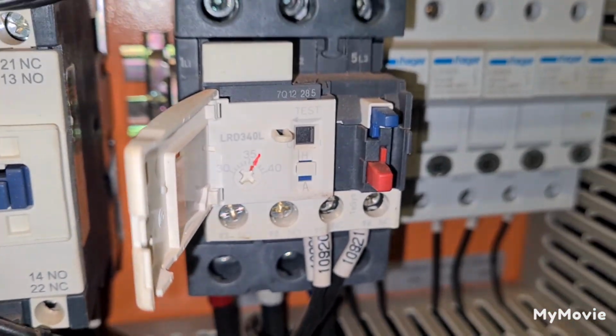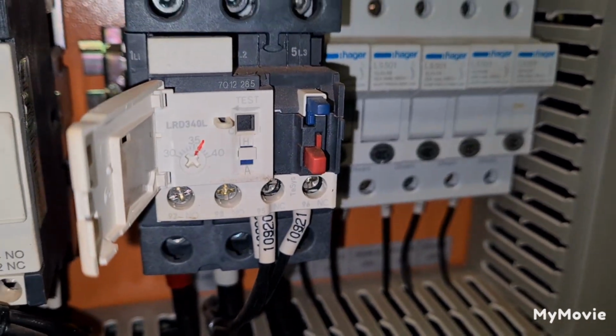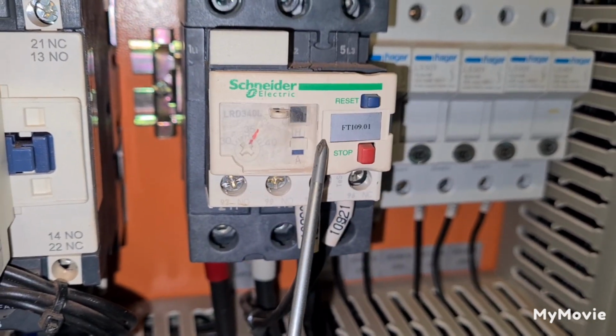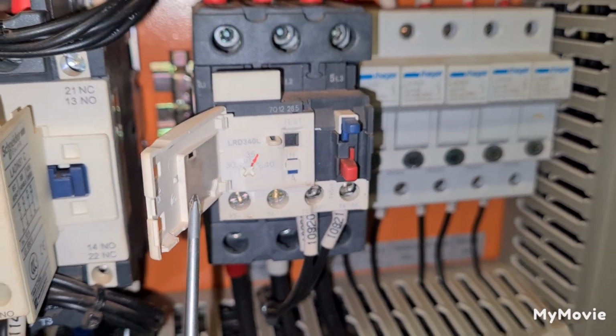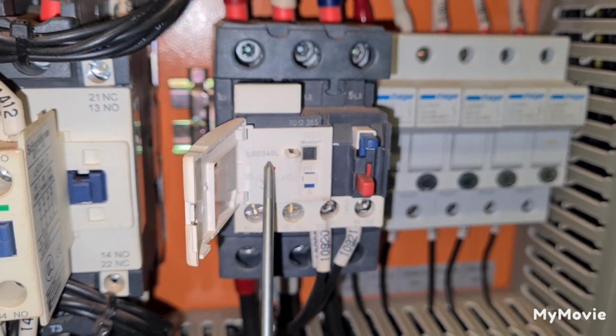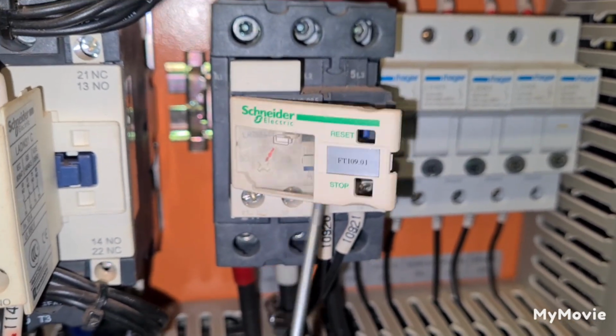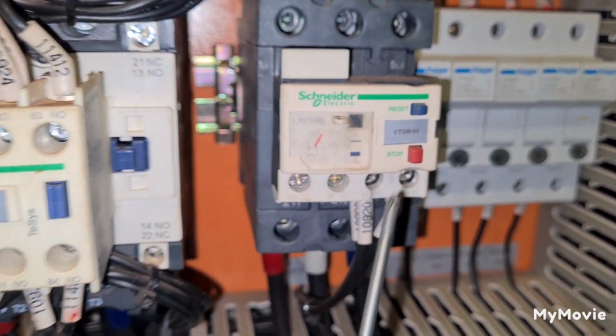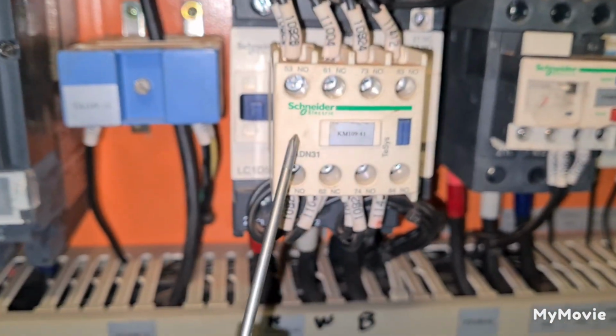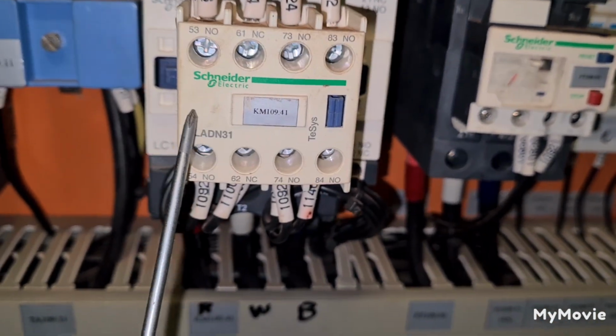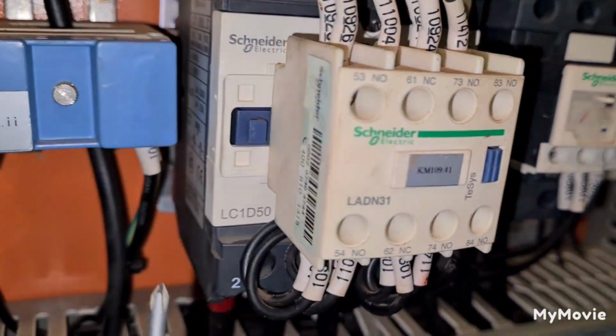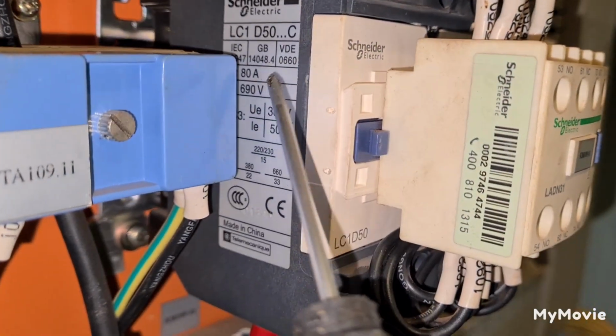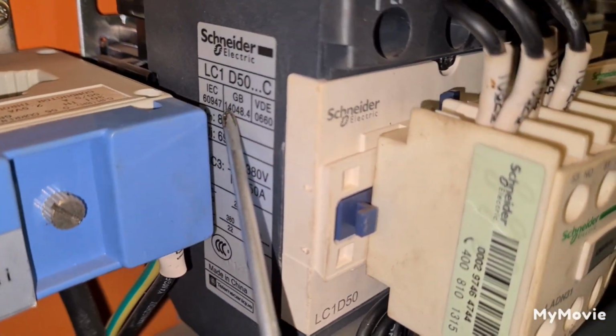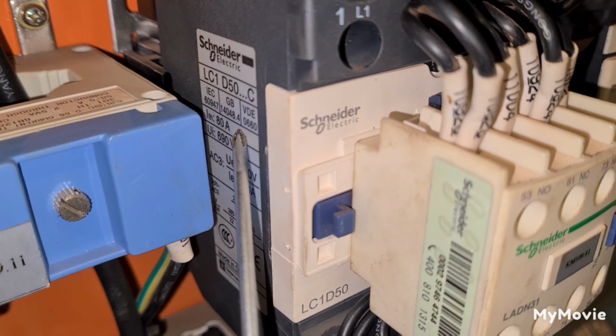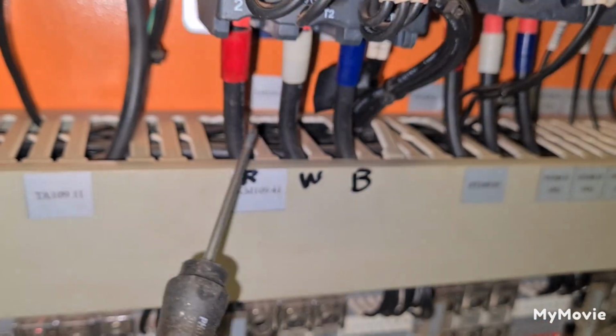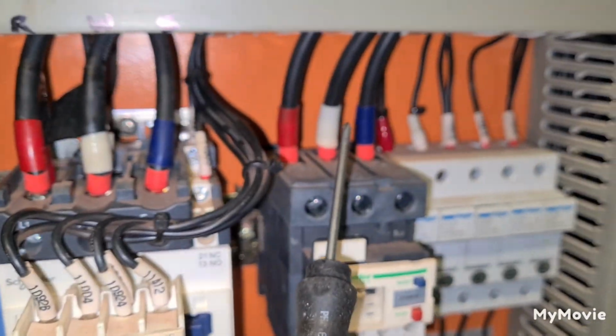Okay, this overload trip or thermal relay is set by 36 ampere, made by Schneider, no? LRD340L overload relay, Schneider. Okay, and then we have the auxiliary contact LADN31 with ITH 80 ampere. See, it has ITH 80 ampere. This is 80 ampere. Take note that my motor is connected on this side going there.